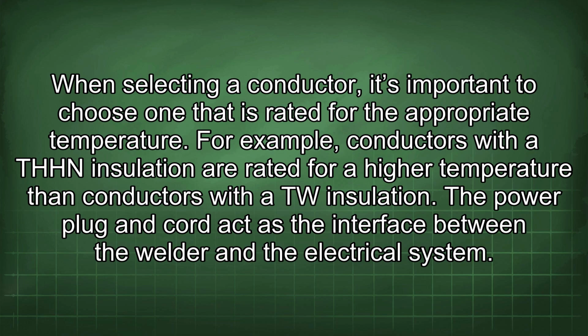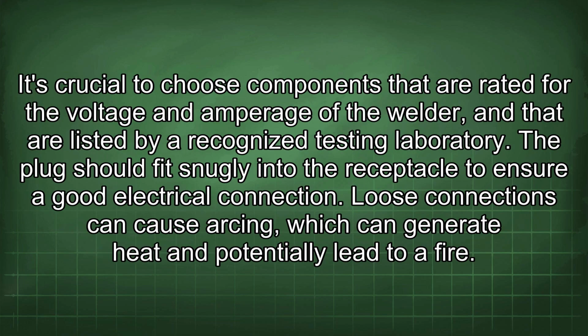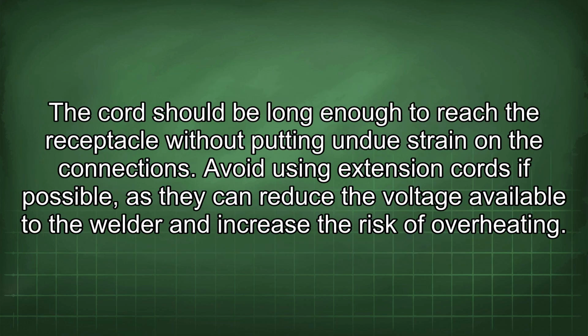The power plug and cord act as the interface between the welder and the electrical system. It's crucial to choose components that are rated for the voltage and amperage of the welder, and that are listed by a recognized testing laboratory. The plug should fit snugly into the receptacle to ensure a good electrical connection. Loose connections can cause arcing, which can generate heat and potentially lead to a fire. The cord should be long enough to reach the receptacle without putting undue strain on the connections.